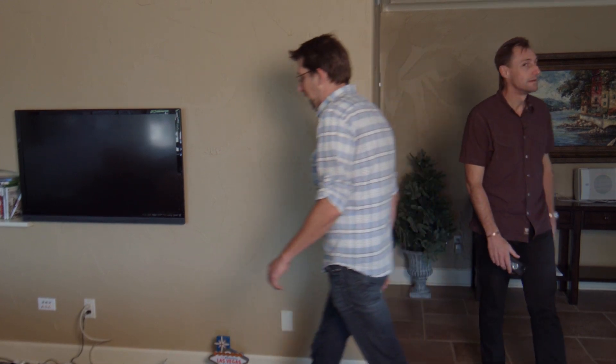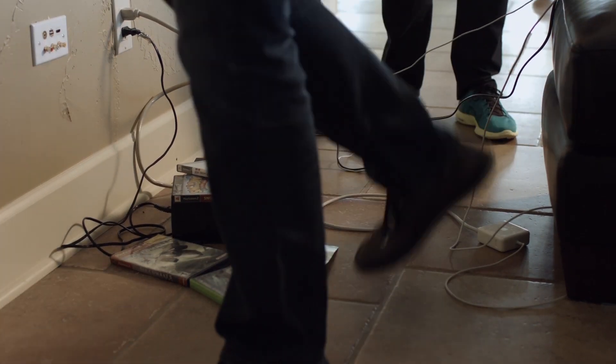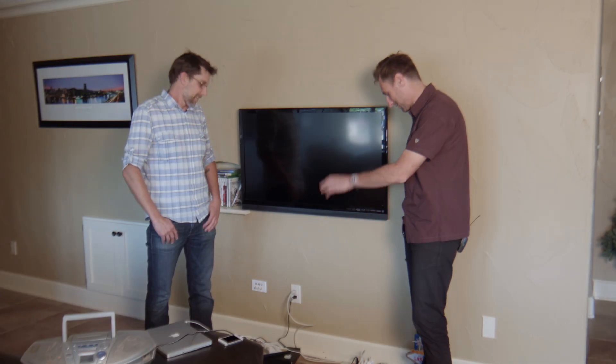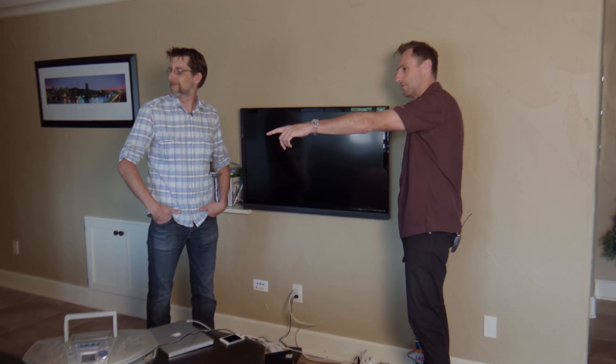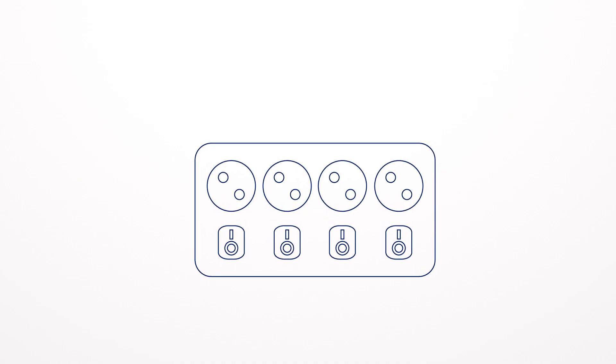So here we are in the boys' rec room. It's exactly what I'm talking about. These guys are definitely the culprits — they've got all sorts of electronics plugged in over here. There's a space heater over there that draws a lot of current. You need to talk to these guys; they're definitely overloading the circuits. Fortunately, your FLIR One gave us the clue when we looked at the breaker panel.